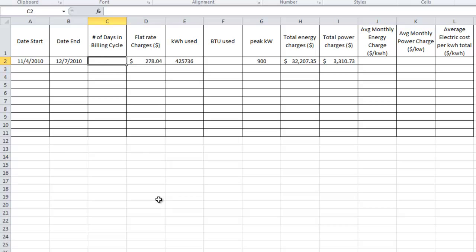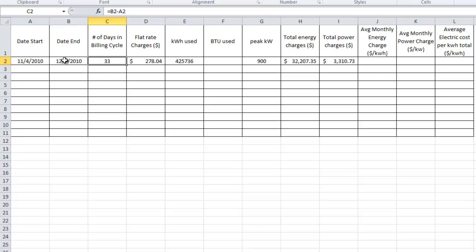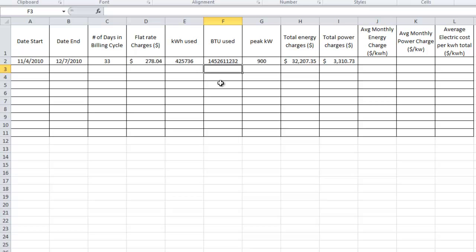Let's go ahead and calculate the number of days in the billing cycle. It turns out Excel, when it stores dates, if you subtract dates it automatically gives you the number of days. In this case it's 33 — I just subtracted A2 from B2. For BTUs used, remembering that there are 3,412 BTUs per kilowatt hour, we take the kilowatt hours used and multiply by 3,412. These two are just two sides of the same coin — kilowatt hours and BTUs, just in different units.